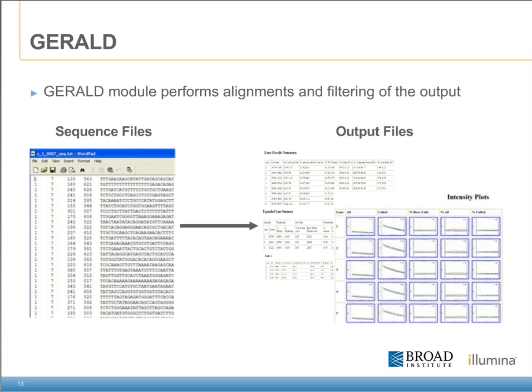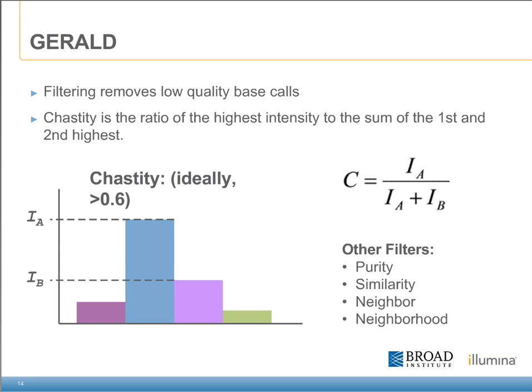As part of the output, a number of intensity plots are generated. These plots can be extremely useful in determining the quality of the samples, the chemistry, and the equipment throughout the run cycles. As part of the Gerald module, some initial filtering occurs in order to highlight the highest quality sequencing reads. Within the software is a chastity filter. This filter looks at the ratio of the highest intensity to the sum of the first and second highest intensity, as shown in the example. During processing, an ideal chastity filter of 0.6 is used to determine which reads are the highest quality. The software does not discard reads that do not pass the chastity filter — a column within the QSeq files indicates which reads pass the filter by a 1 or 0 designation.